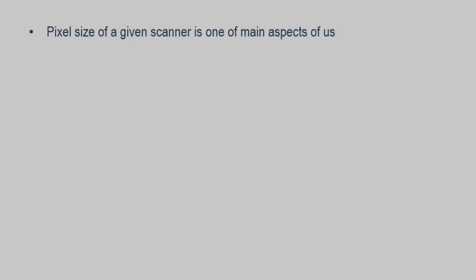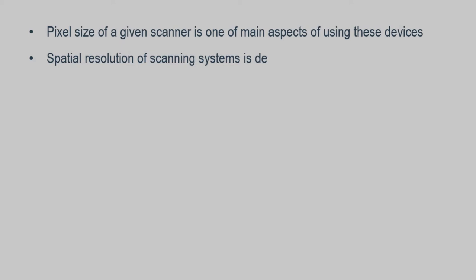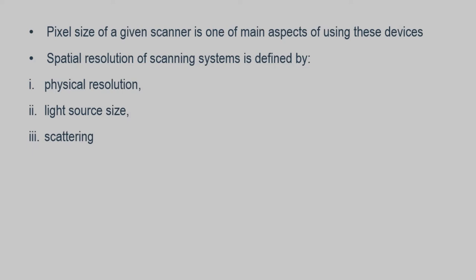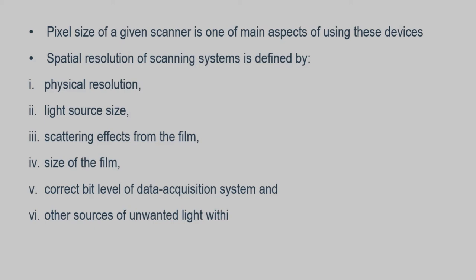The pixel size of a given scanner is one of the main aspects of using these devices. Spatial resolution of a scanning system is defined by: one, physical resolution; two, light source size; three, scattering effects of the film; four, size of the film; five, correct bit level of the data acquisition system; and six, other sources of light within the scanner.